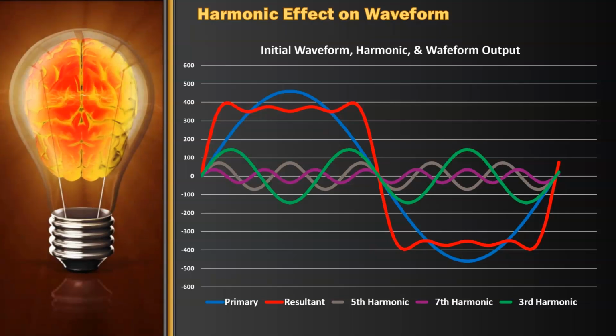So there's an initial waveform, blue line, 60 hertz waveform. And you can see there's a third, a fifth, and a seventh harmonic. What happens with those is that when you add up all that energy, it produces a waveform that looks sort of flattened on the top. And that's the red line that you see. It does another thing that I just want to point out to you. If you looked at it on an oscilloscope or a power meter or something like that, you get a waveform that looks like that. It'll be flattened on the top for some reason, in some ways.